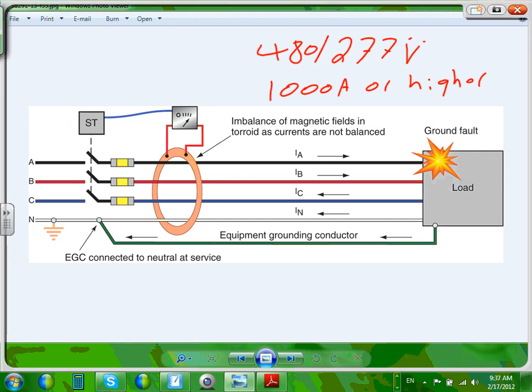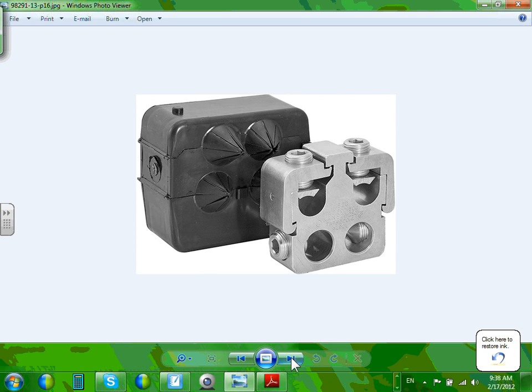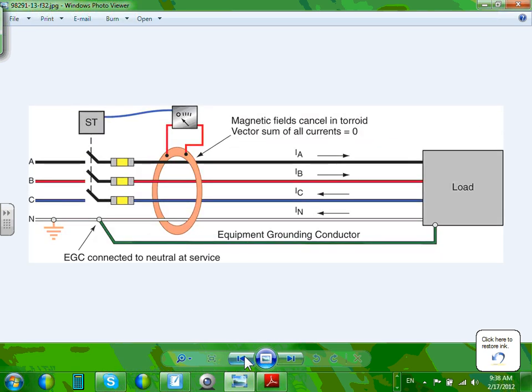There could be, under certain circumstances, a current. If you have a ground fault right here, the current coming on the ground could be high enough to create a fire in the building without the circuit breaker being able to interrupt it. So the smart people decided to put ground fault protection on equipment like this. CT cabinet.